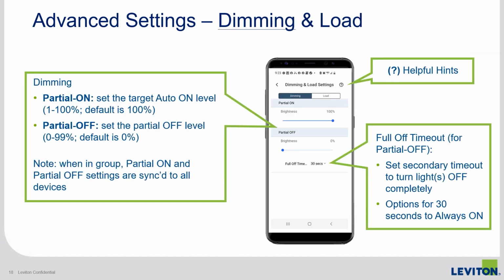If connected to a 0 to 10 volt dimming fixture, you can enable partial on, partial off levels and set minimum and maximum trim levels under the dimming and load section. First, let's look at the dimming updates. You can set partial on levels where you want the lights to initially turn on using a slider bar to set this level. 50% is common in many applications requiring multi-level lighting controls to meet energy code requirements.